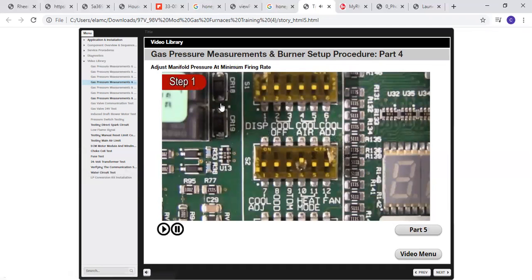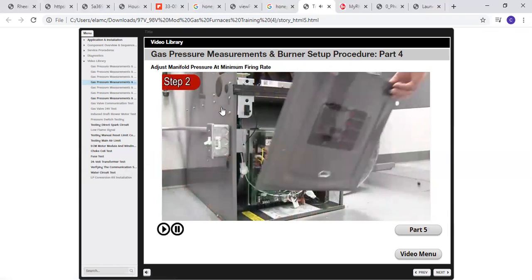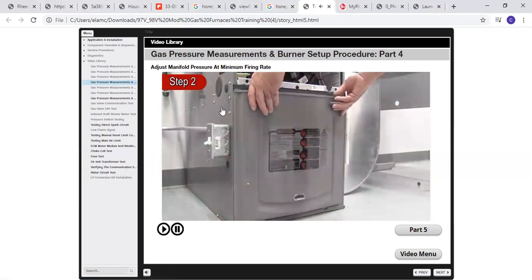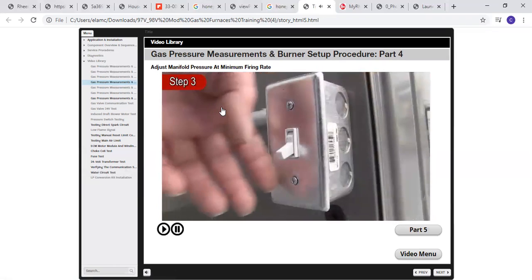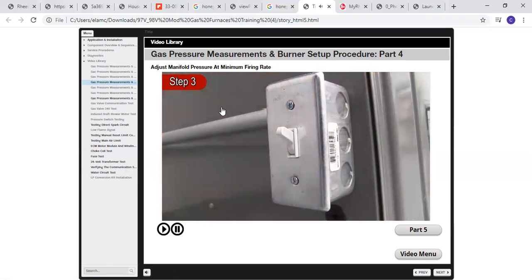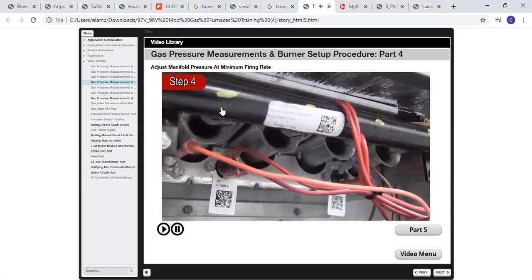We'll go over to do the minimum. Set dip switch SW10 to the on position and dip switch SW11 to the off position. This will force the furnace to operate at the firing rate of 40% volume. Step 2. Replace the blower compartment door. Step 3. Connect furnace electrical power supply.